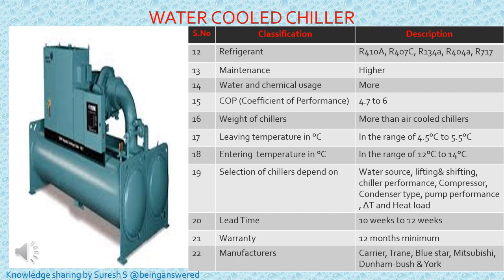Similarly, the maintenance of the chiller will be higher compared to the air cooled chiller, and water and chemical usage will be more. The coefficient of performance always plays a major role in selecting the chiller. For water cooled, it will be 4.7 to 6. The weight of the chiller will be very heavy.